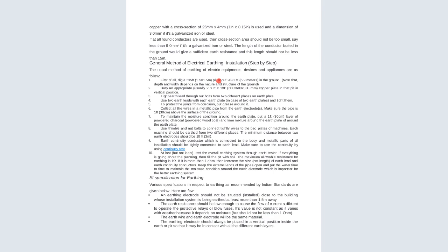So the general method of electrical earthing, a step-by-step way of installing. The usual method of earthing in electrical equipment, devices and appliances is as follows. Step number 1 is, first of all, dig a 5 by 5 feet pit about 20 to 30 feet in the ground. Now note that the depth depends on the nature of the structure of the ground. The second step is to bury an appropriate, that is usually a copper plate, in the pit in a vertical position. Make sure you bury it in a vertical position, and then tighten the earth lead through the nut bolts from 2 different places on the earth plate.